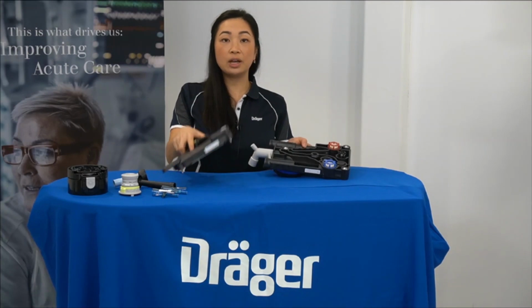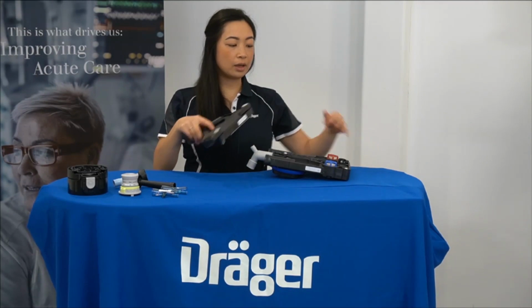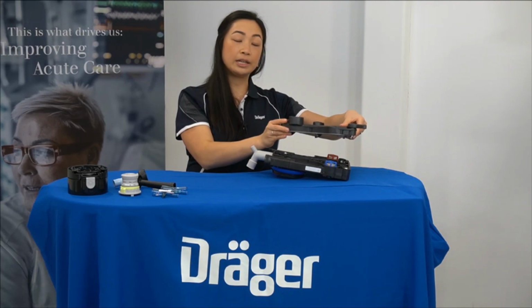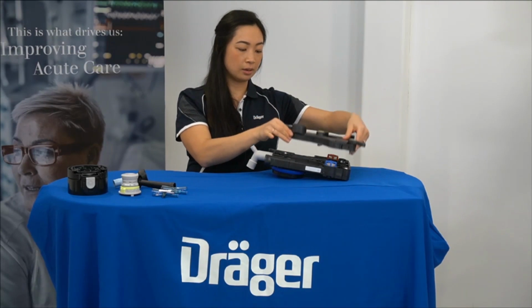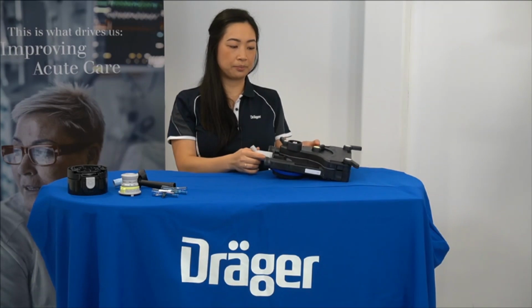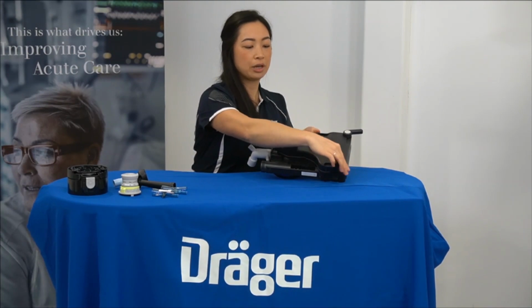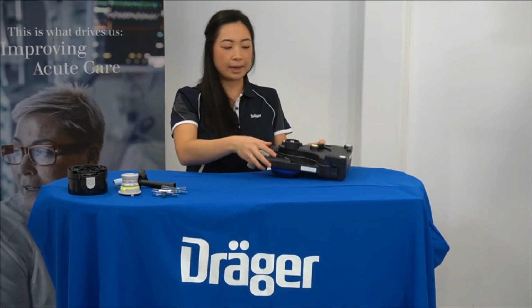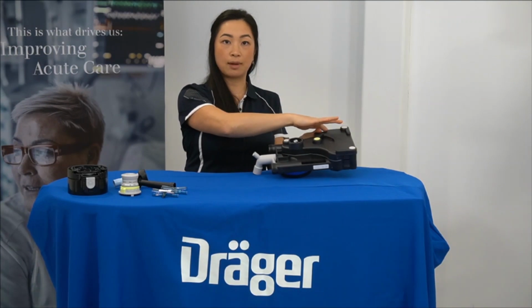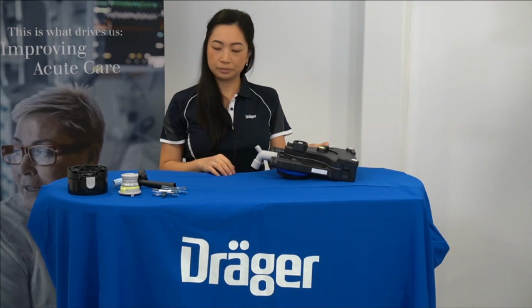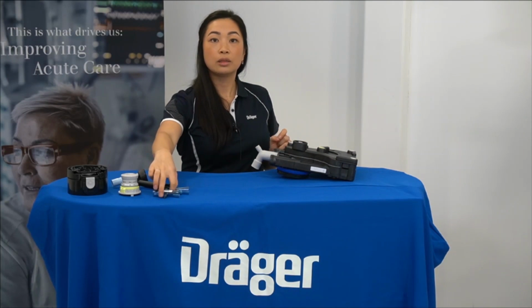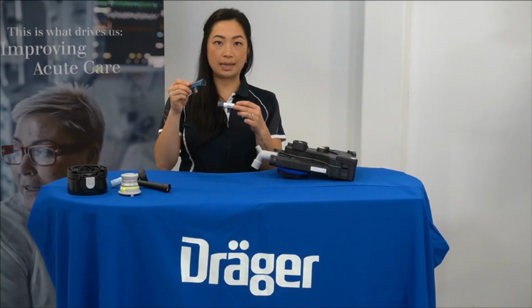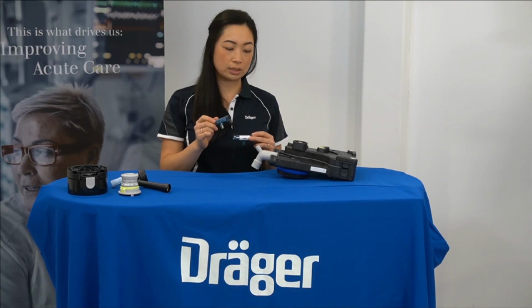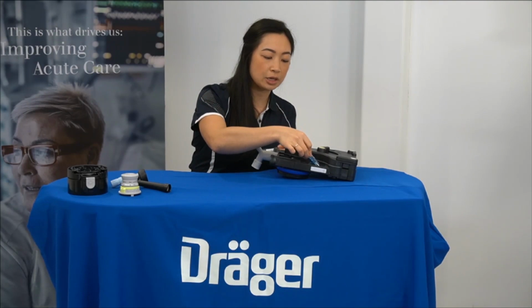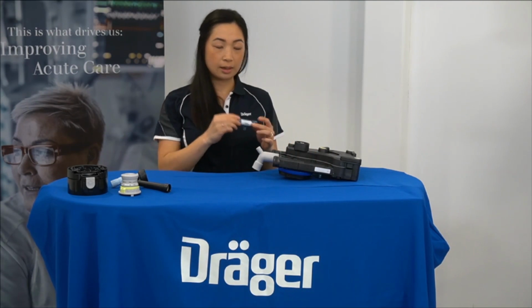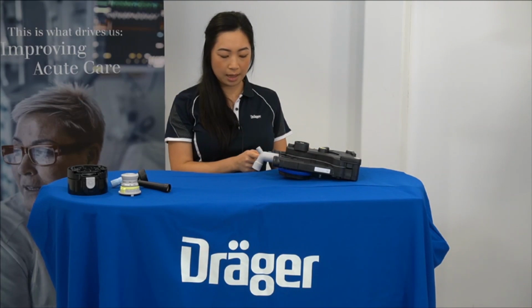Then, to replace the cover of the breathing block, align the cover up with the base and ensure the grey levers remain open so that it can be attached properly. Then, close the three grey levers and ensure there's a proper seal around the top and the base. Then, the clean flow sensors can be placed in the inspiratory and expiratory ports, with the expiratory one inserted from the middle of the port and the inspiratory one inserted from the end.